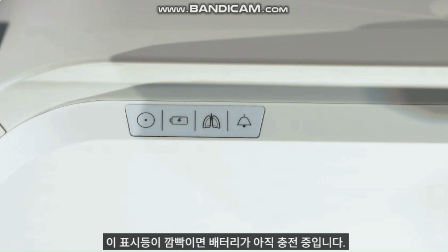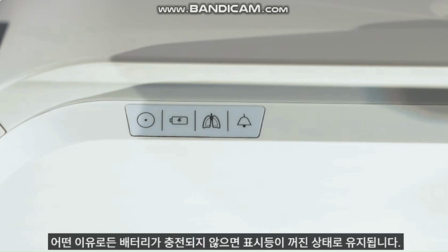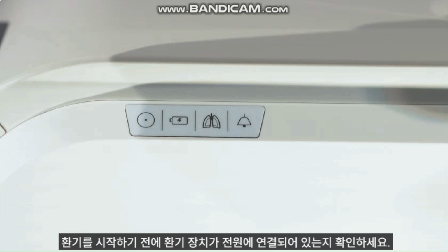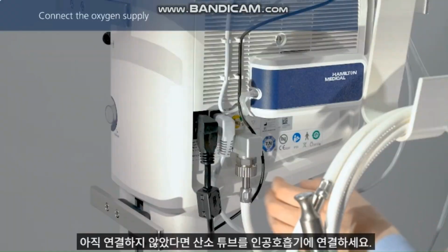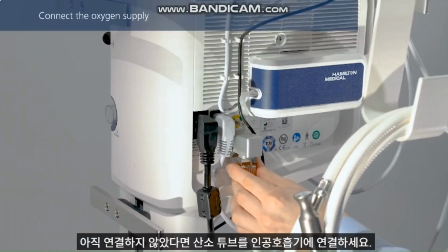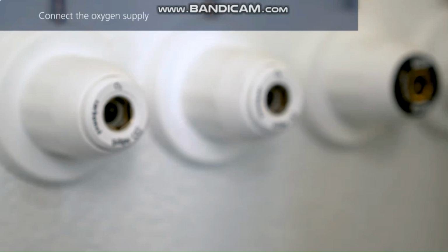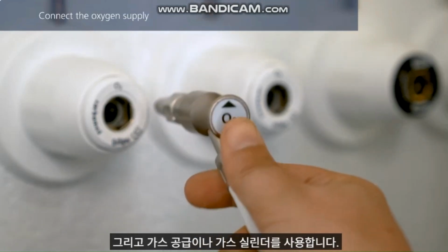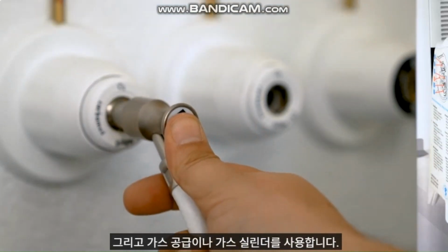When flashing, it means that the battery is still charging. If the battery is not charging, for whatever reason, the indicator will remain dark. Make sure the ventilator is connected to a power source prior to starting ventilation. If you haven't done so already, connect the oxygen hose to the ventilator, and then to the gas supply or a gas cylinder.